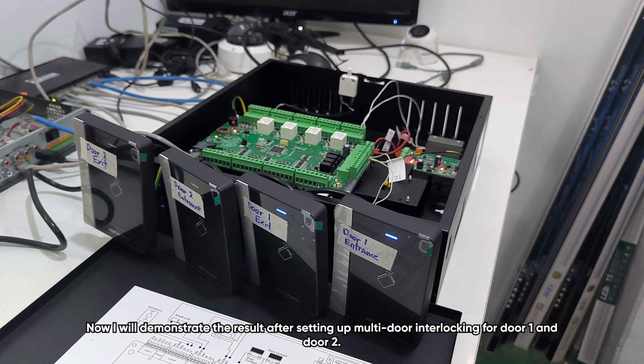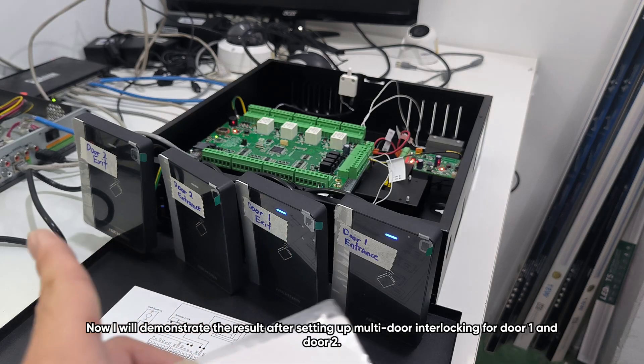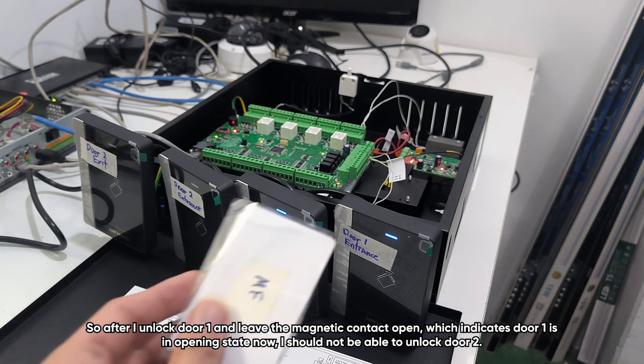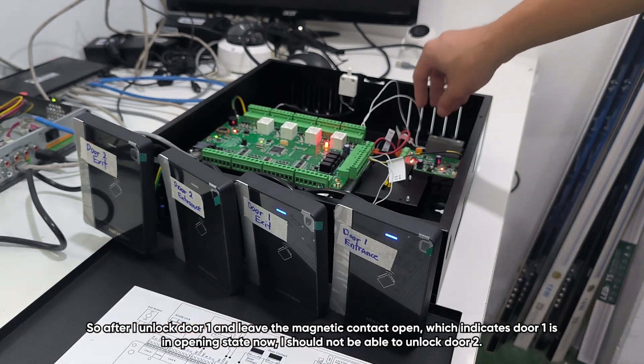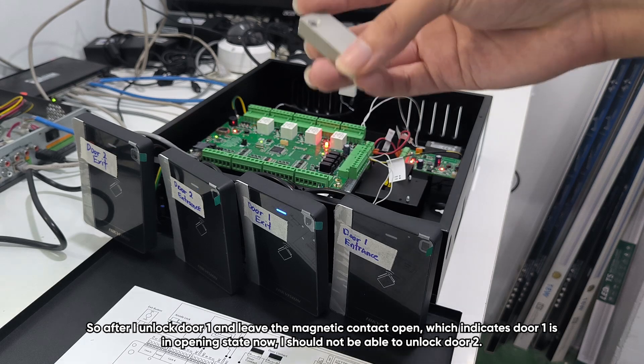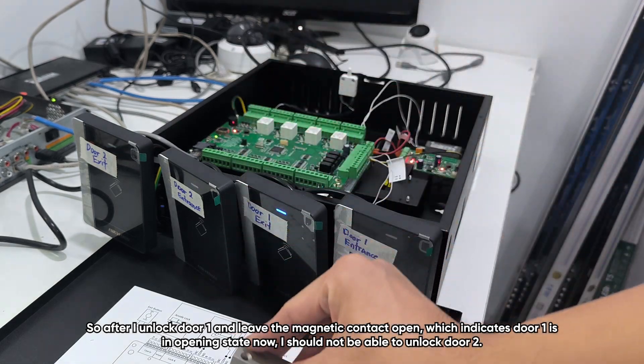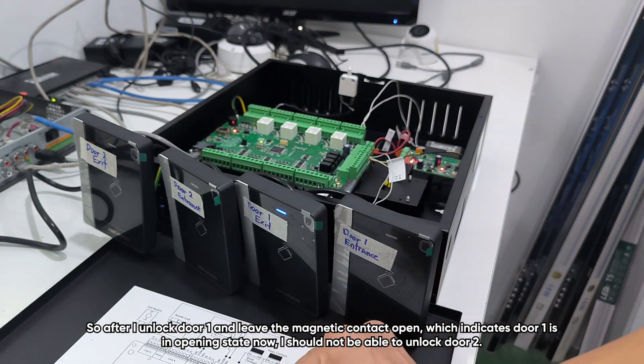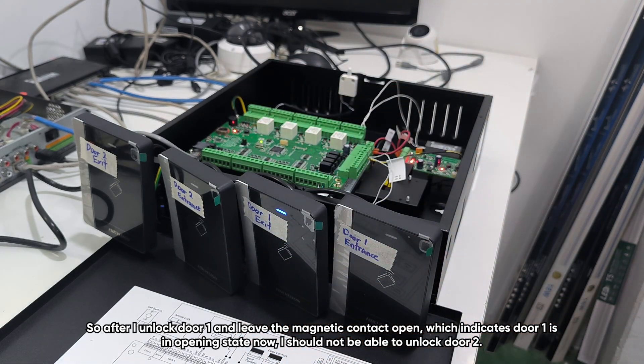Now I'll demonstrate the result after setting up multi-door interlocking for door one and door two. So after I unlock door one and leave the magnetic contact open, which indicates door one is in opening state now, I should not be able to unlock door two.